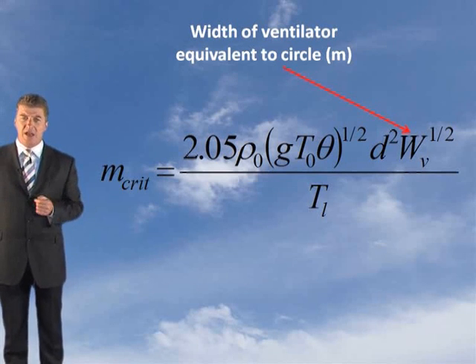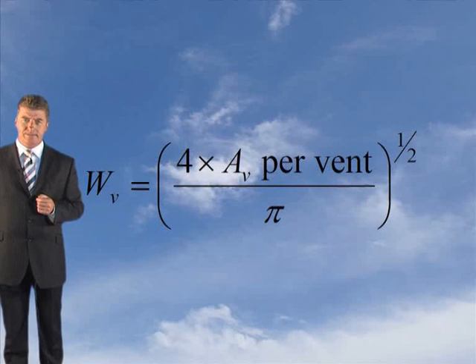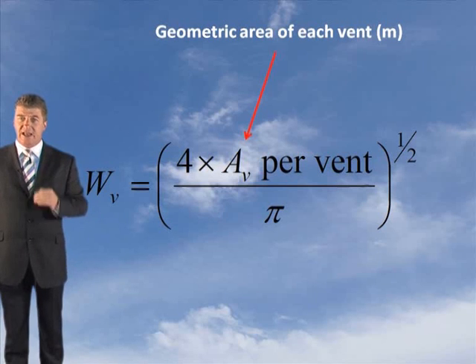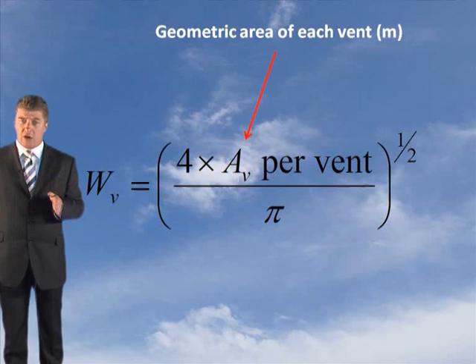Now you've got to determine WV and this is the formula to apply. WV equals 4 times AV per vent, now this is the geometric area, this is once you've taken into account the efficiency of the ventilator, divided by π and the whole lot square rooted.